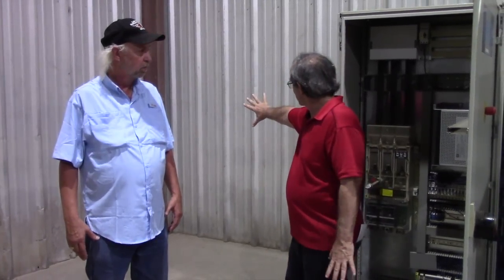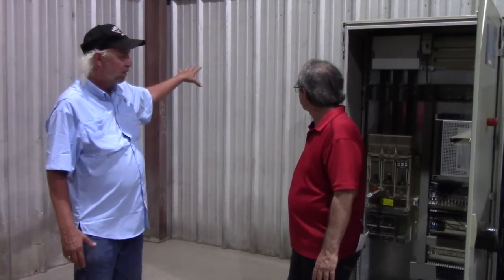The disconnect goes right here, sitting outside the building, giving first responders the ability to disconnect the entire power supply to the plant before entering the facility. The National Electrical Code changed in 2011, requiring any new installation to have a fusible disconnect between the transformer outside the building and the switchgear inside.